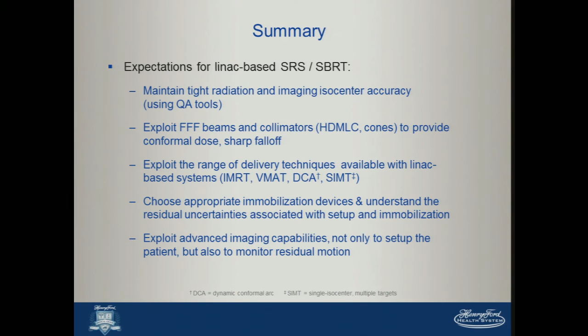So, in summary, the expectations for a Linac-based SRS SBRT platform are to maintain tight mechanical isocenter accuracy, exploit the flattening filter-free beams and collimators to provide conformal dose and sharp fall-off, and exploit the range of delivery techniques that you have available to you with the treatment planning systems. You need to choose appropriate immobilization devices and understand the residual uncertainties associated with those, and exploit the advanced imaging capabilities in particular, not only to set up the patient, but to monitor residual motion and understand your geometric uncertainties.